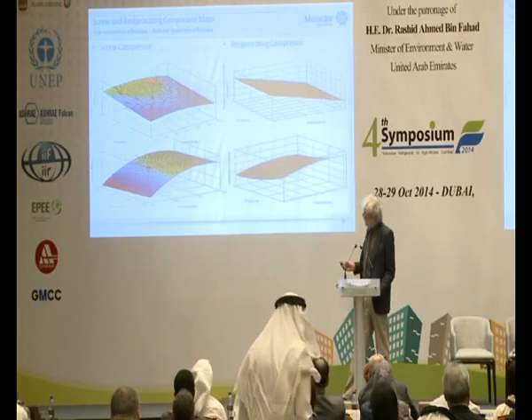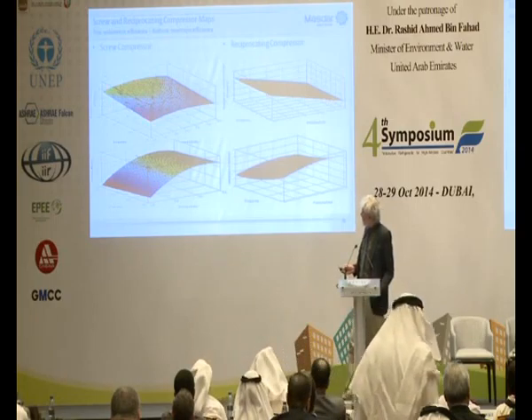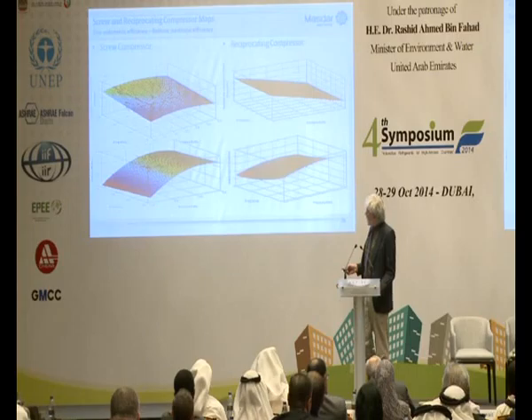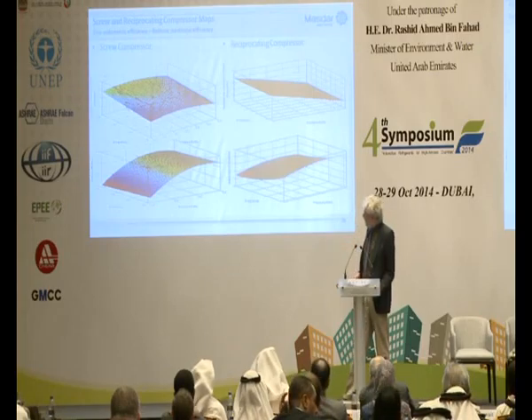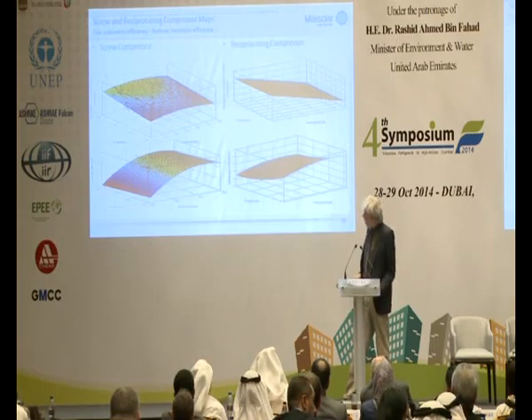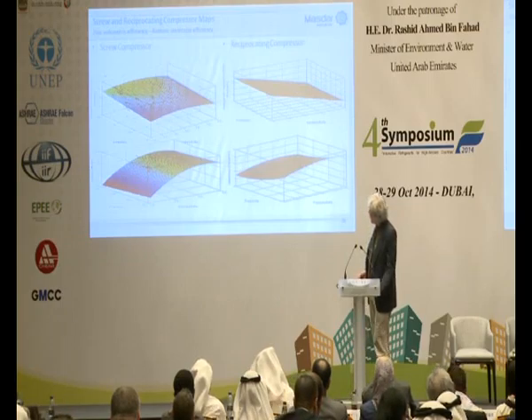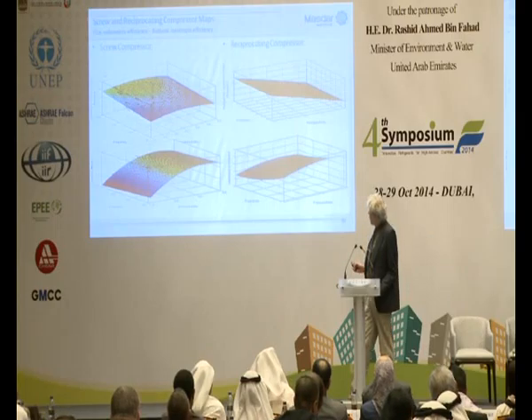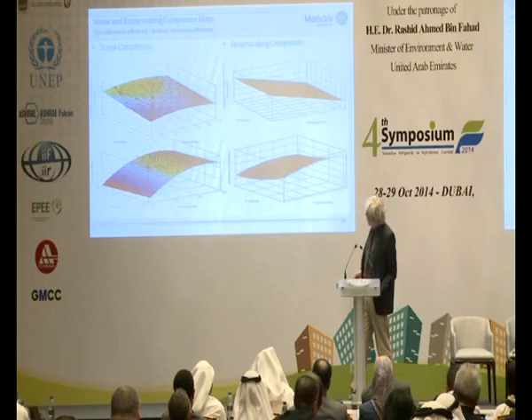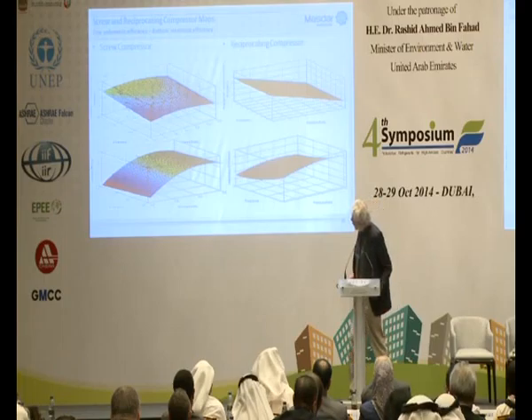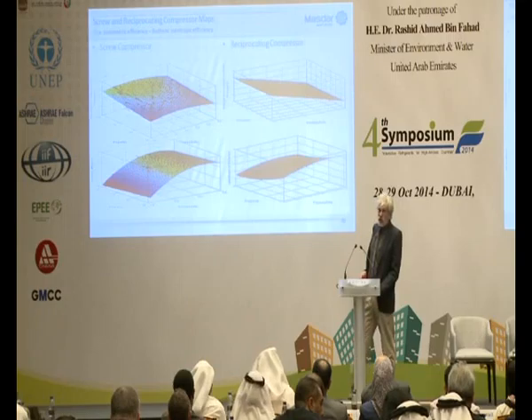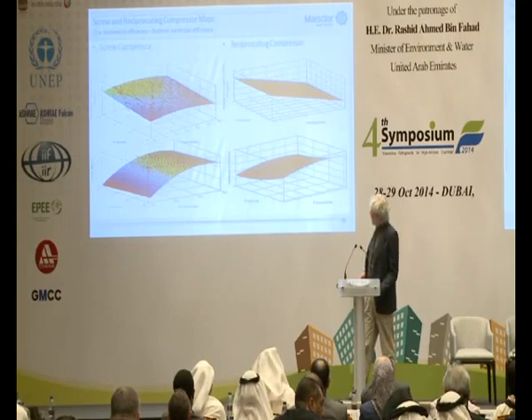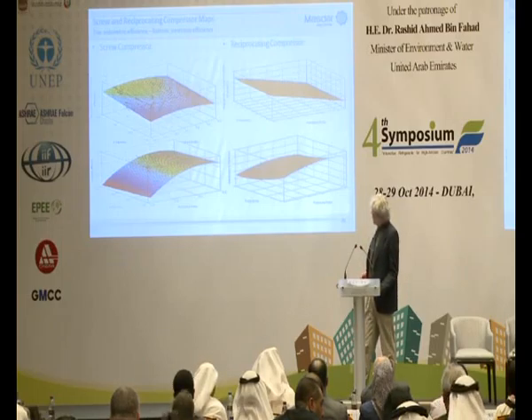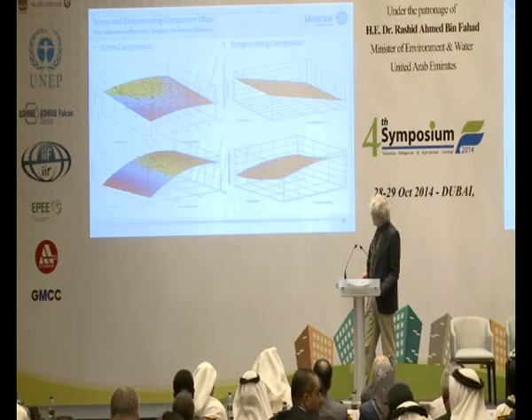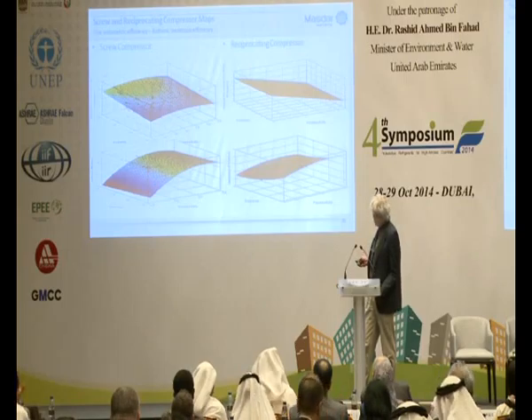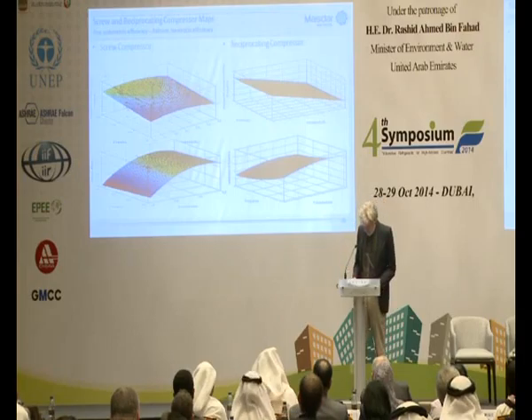The volumetric efficiency is fairly flat. The isentropic efficiency, this is typical of a screw compressor. It drops operating above its optimal pressure ratio, and it drops rather rapidly below the design pressure ratio. On the right-hand side, you have similar models. And it's interesting to contrast the two. So the volumetric efficiency is dropping with frequency on the screw compressor, primarily due to back leakage. It's rising with the reciprocating compressor due to reduced flow friction losses. And even more important is the isentropic efficiency, which is quite flat with pressure ratio for the reciprocating compressor. So we'll come back to that a little bit later.